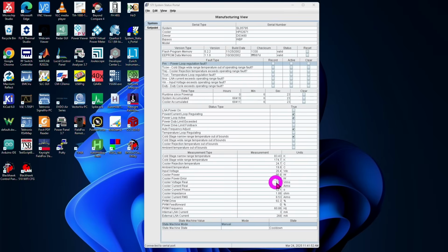And we're dumping just under 100 watts into the cooler. So this can go all the way up to 125, 130 is where I've set the limit. Some people push it even harder, but I don't think we need to do that for our purposes. Now, even though it only took 6 minutes to reach this temperature, it's going to take a lot longer to go from 171 Kelvin to 70 Kelvin. Now remember, you have to subtract 10 degrees from this because of the offset. So we're already pretty cold in there. And now after 35 minutes or so, you can see that we are within the range of the narrow temperature measurement. Now keep in mind again that you have to subtract about 10 from this, so it's really cold in there. We're dumping 126 watts into the engine, which is roughly the maximum I have entered there. Yeah, it's going to continue working.